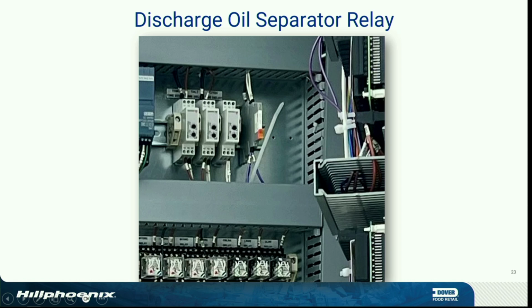And the defrost. But anyway, the new one, that's all it does. That's all it needed to do. We used to have all of our alarms. When he gets a low receiver alarm, or he'll get a low separator alarm, there's no such thing as a low separator, right? Separator's always low until it's full and we pump it out. But the low separator was actually the reservoir, because it all comes into that separator flex combiner, and anything that goes out is going to be separator, because that's how it's going to alarm. So a high separator is true. A low separator would be your reservoir. Right? Just misnumbered or mislaid.